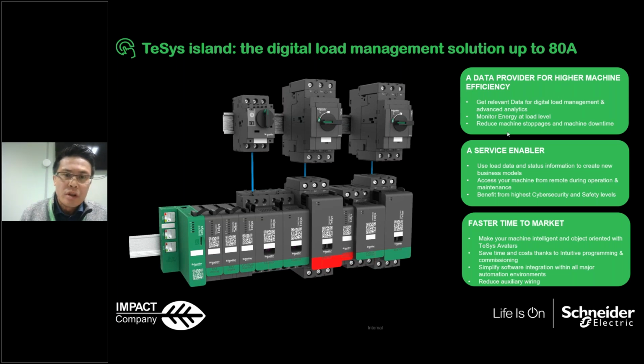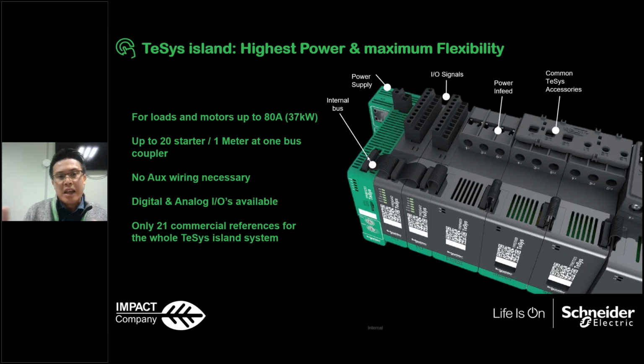And then, what is it? TeSys island is a load management system up to 80 amps. So for any motors below 37 kilowatts, you can use the TeSys island to control. We basically have different motors or different starters. We have the contactor inside, so we control the motors with the contactors. Every single starter is connected to the screen part, what we call the bus coupler. This bus coupler gathers all the information internally with this ribbon cable and then communicates to the system or to the PLC via Ethernet IP, Modbus TCP, or Profibus. So everything is connected over Ethernet. One bus coupler you can equip with a maximum of 20 starters.